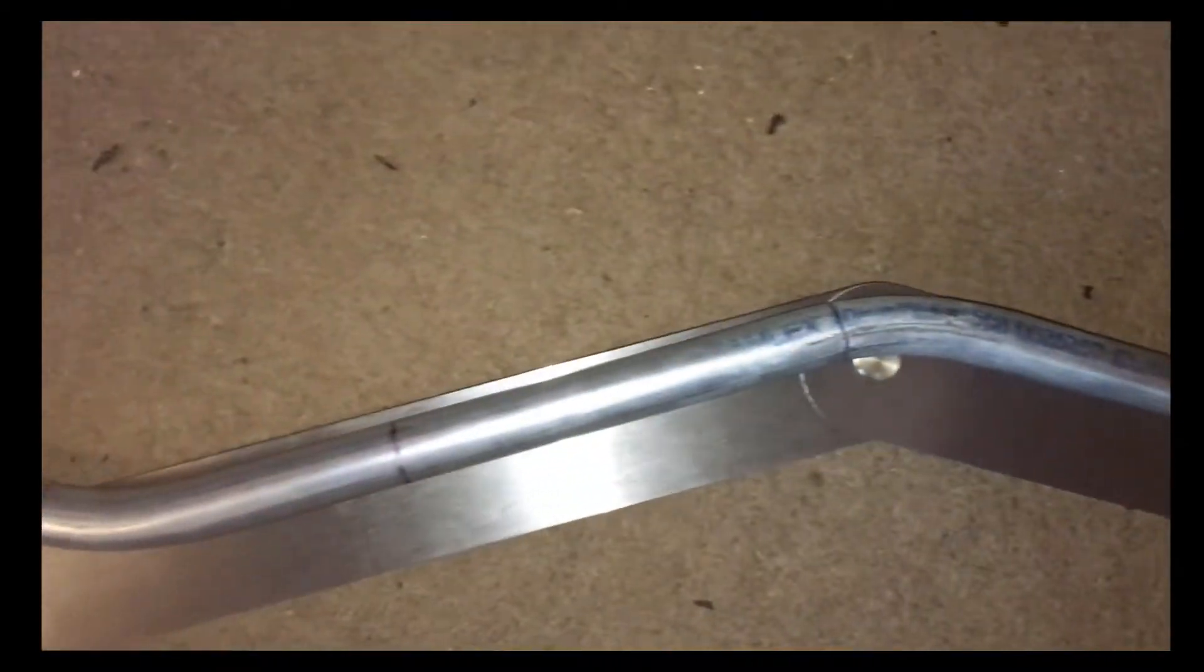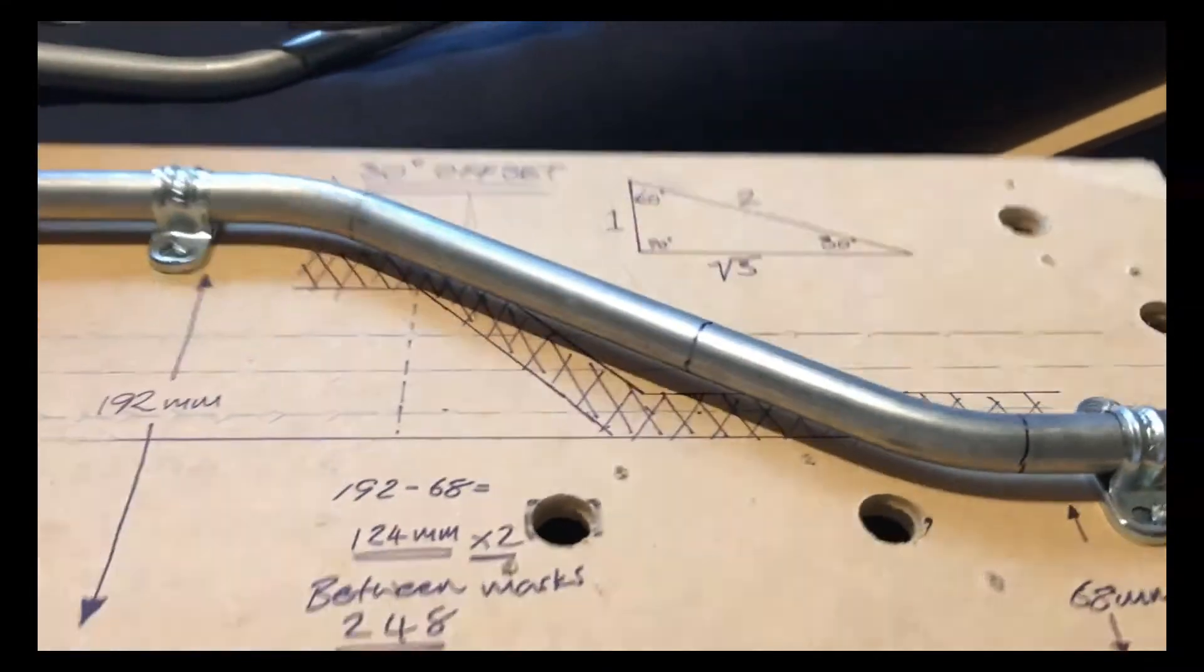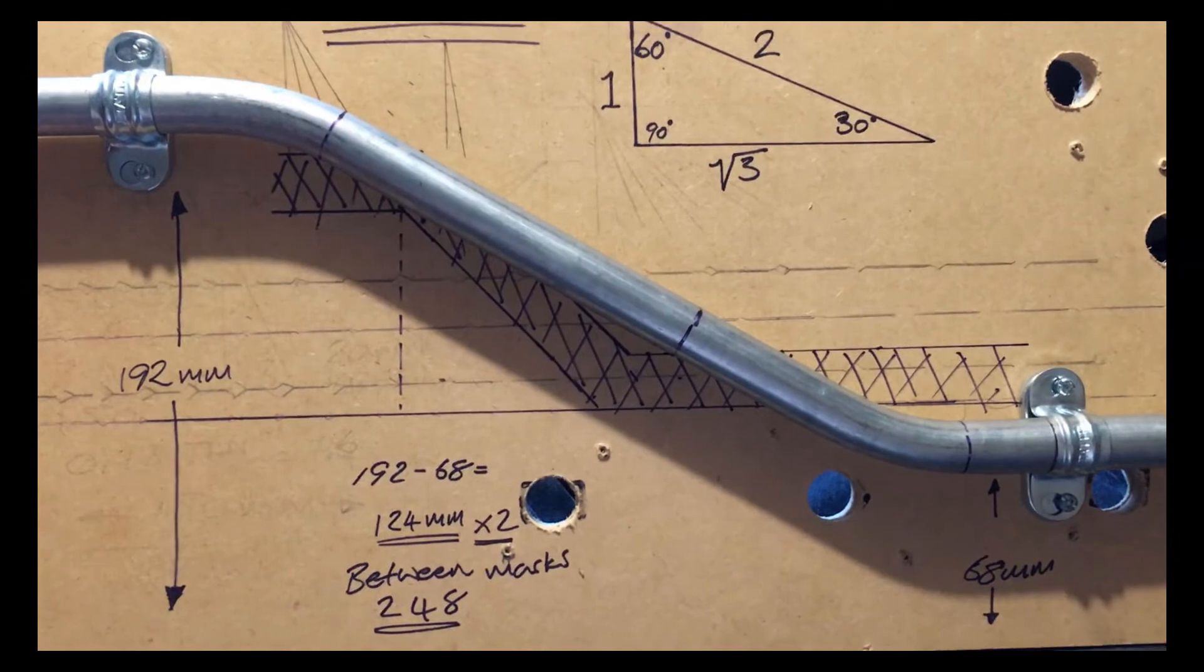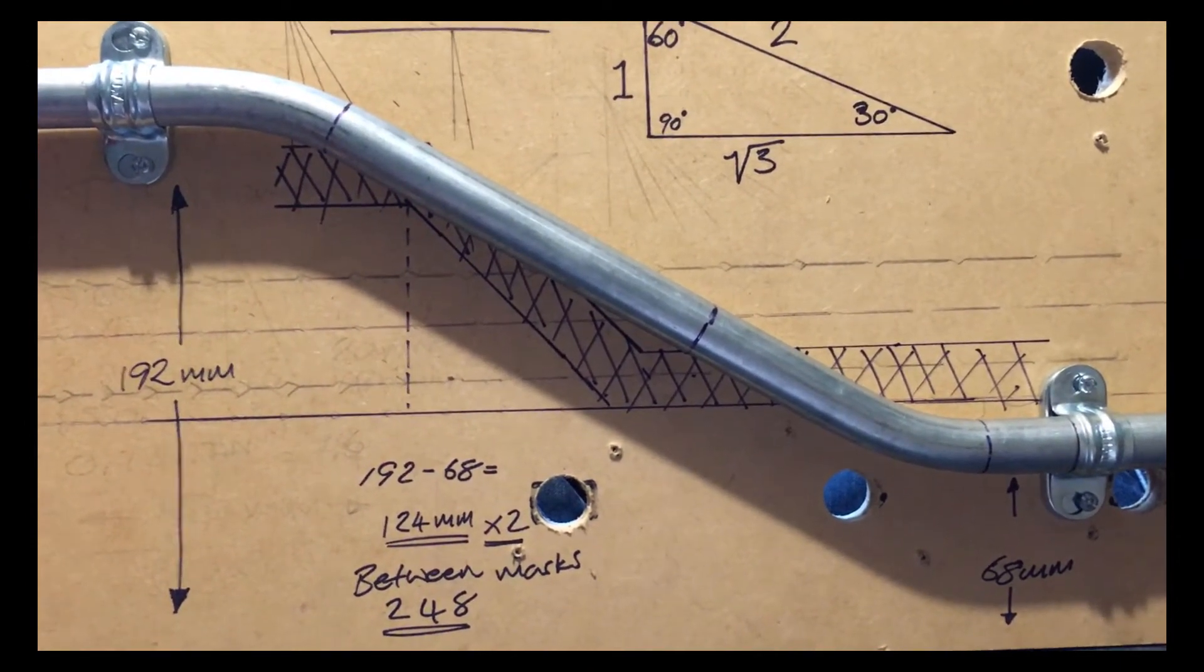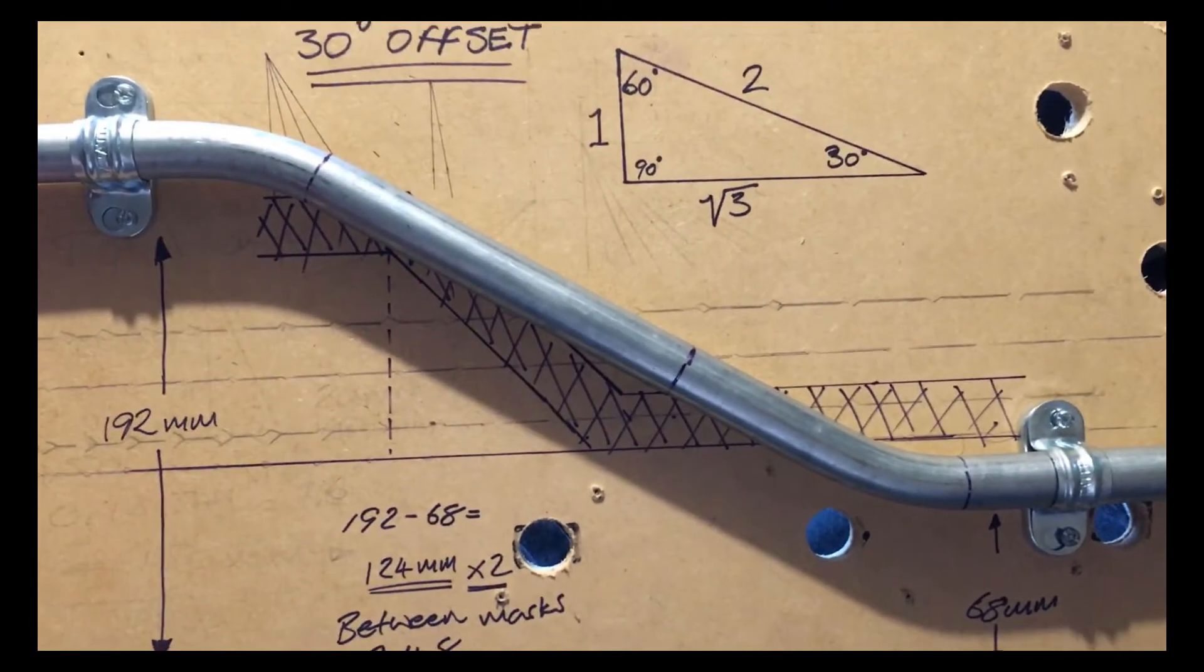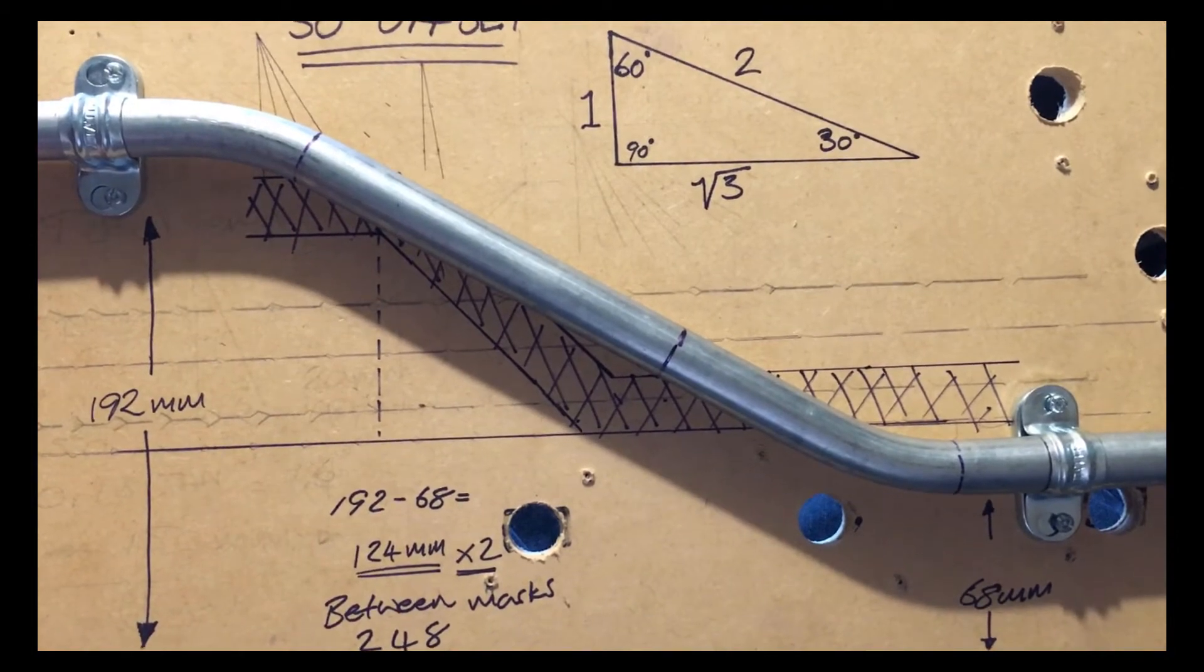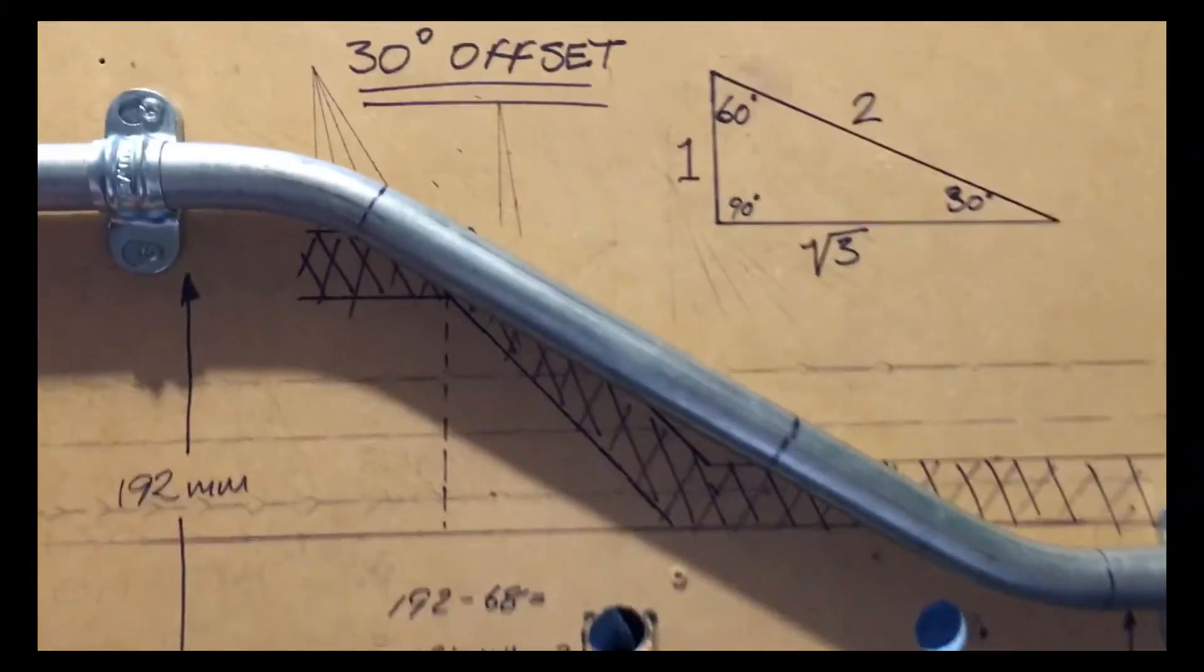So here you can see the finished product. It didn't take too long to do - it requires some mucking about, over bending and under bending it a little bit to get it to fit, but it seems fairly accurate. Yeah, it seems to work alright. So that's a 30-degree offset bend.